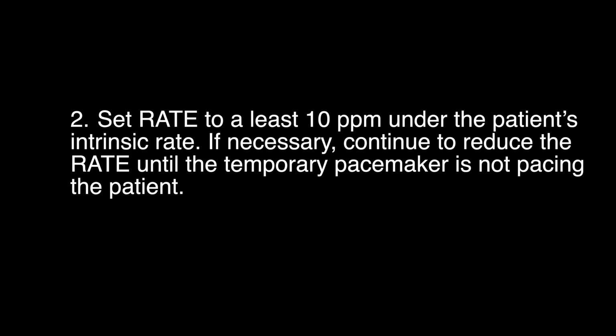Determining atrial or ventricular sensing threshold. Only use this procedure on patients with adequate intrinsic rhythm. To determine atrial or ventricular sensing threshold, perform the following steps. 1. Turn on the temporary pacemaker without connecting it to the patient lead system. Caution: do not connect the temporary pacemaker to the patient lead system until step 4. 2. Set rate to at least 10 ppm under the patient's intrinsic rate. If necessary, continue to reduce the rate until the temporary pacemaker is not pacing the patient.